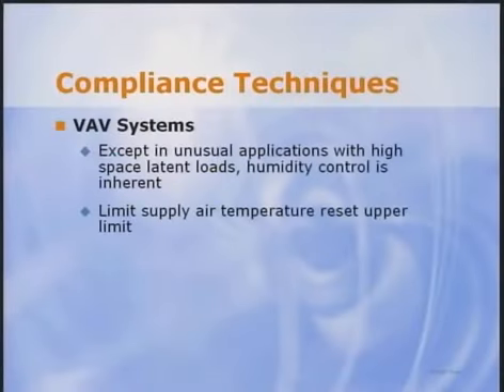First, what about VAV systems? As Dennis showed, for almost all applications, humidity control is inherent with VAV systems. No special features or controls are required. One caveat though, if supply temperature reset is used based on zone demand for systems in humid climates, make sure the warmest supply temperature still provides dehumidification at the coil. The upper supply temperature limit can be reset based on space or return air relative humidity, or it can be reset by outdoor air temperature to ensure that colder supply temperatures are maintained when outdoor air humidity is or can be high.